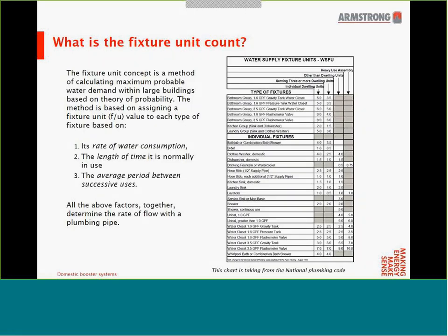So what is a fixture unit? The fixture unit is a method of calculating the maximum probable water demand within a large building based on the theory of probability. The method assigns a fixture unit (FU) value for each type of fixture based on: the rate of water consumption, the length of time it's normally in use, and the average period of time between successive uses. Keep in mind that a fixture unit is not a flow rate, but a design factor — this is very important.